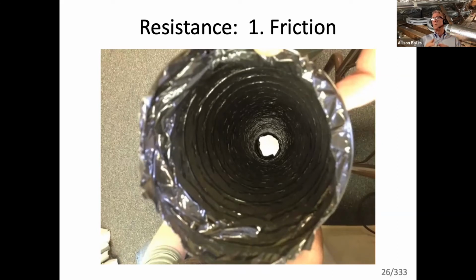You can put it through rigid duct board with the fiberglass on the inside, and that's not very smooth. And there will be a lot of resistance there. You can put it through flex duct, and that may be nice and smooth, or it may be rough, depending on how it's installed. The flex duct, of course, the inner liner needs to be pulled really tight to make it nice and smooth on the inside. And when you do that, it works almost as well as hard pipe, but that doesn't often happen.